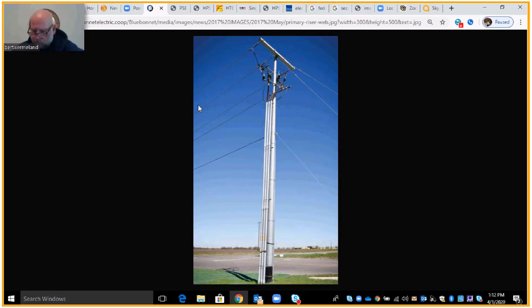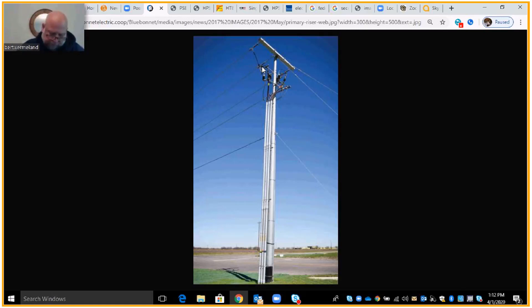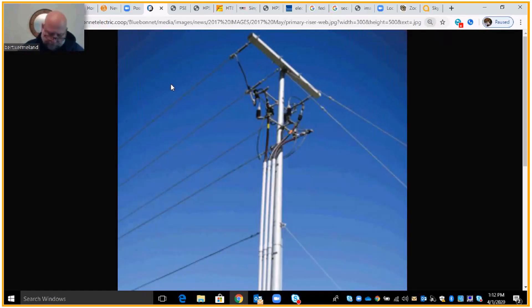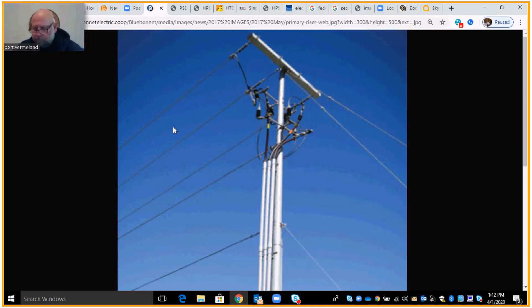A dip pole is a transition from overhead to underground. You'll see the overhead primaries coming in to the dead end, then going down to what they call a terminator, and then underground through conduits to wherever they need to go. Similar to the college — overhead encompasses around all of the college, and at certain points you'll see where the primary goes underground and into the college grounds. This is dipping overhead to underground.